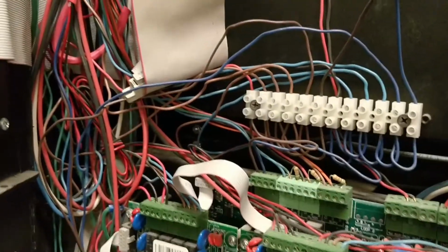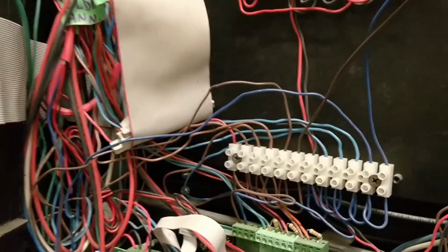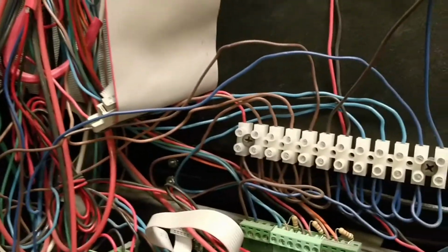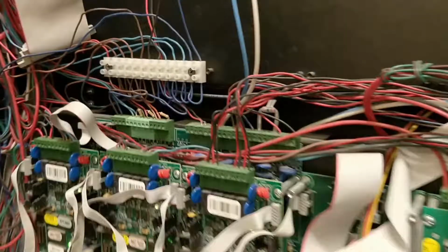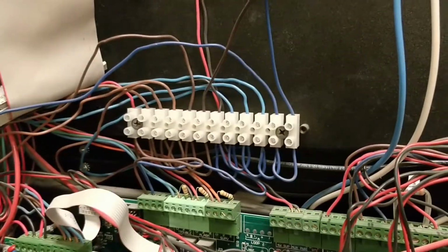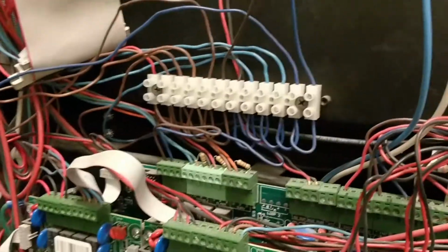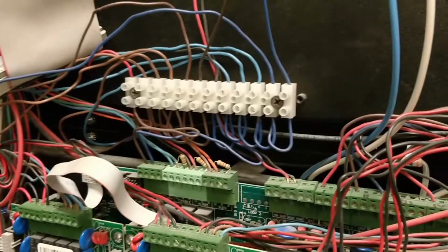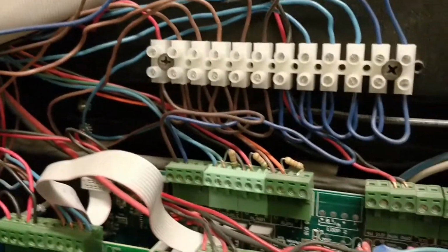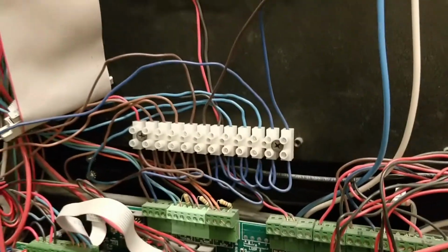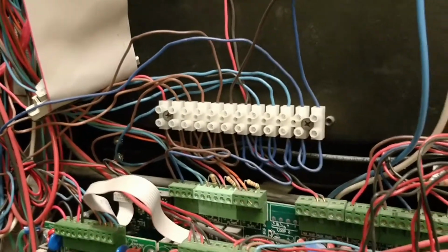I don't see how it could have possibly been easier to run every single wire back to this panel instead of just going to one annunciator and then out of that annunciator to the next one and so on and so forth, and then you put your end of line for the RS-485 in the last annunciator. This one, they just T-tapped it all and they put the end of line in the main annunciator at the front door.